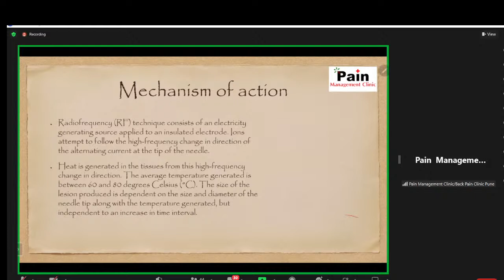The size of the lesion produced depends on the diameter of the probe along with the temperature generated, but is independent of increasing the time interval. That means if you keep the time at 90 seconds, even if you increase it to 100 or 120 seconds, the lesion is not going to increase. There is a lot of literature showing that the maximum lesion you can achieve is at 60 to 90 seconds. This is a common radio frequency probe with an insulated shaft and an active tip, and the whole needle is insulated.